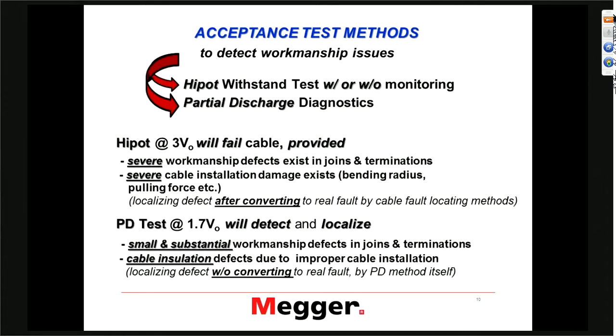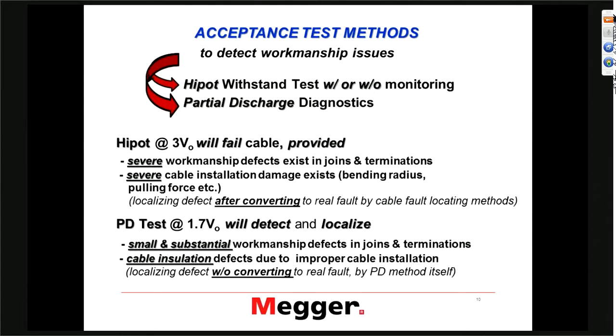A monitored hipot test gives you more information than just a plain go/no-go hipot test. If we really want to see how good or bad a cable is, the PD test is a very, very good tool. Because it cannot only tell us how bad or good it is — it can also, as the only test method overall in all cable testing, tell us where the defect is. It can localize the problem.